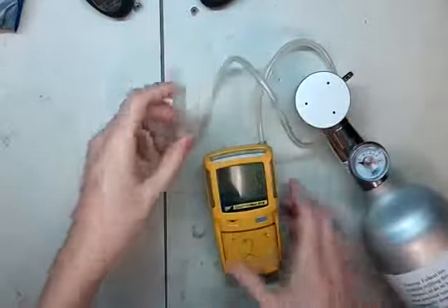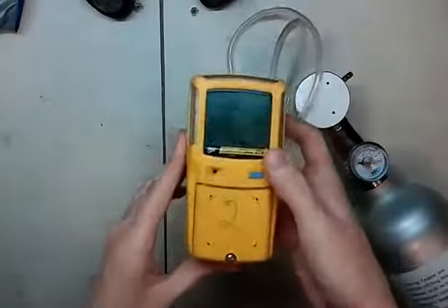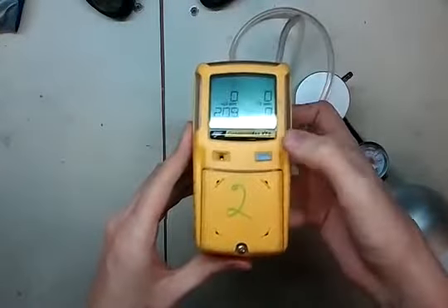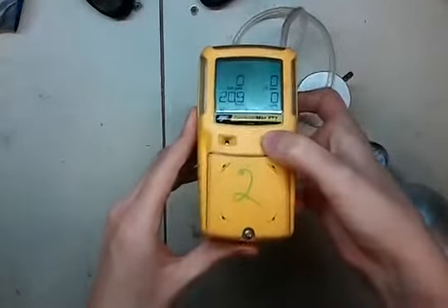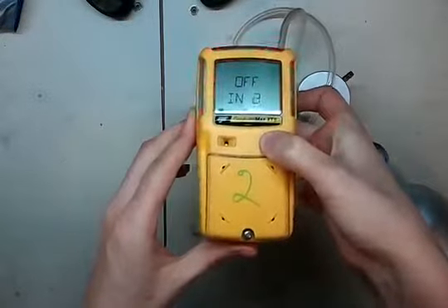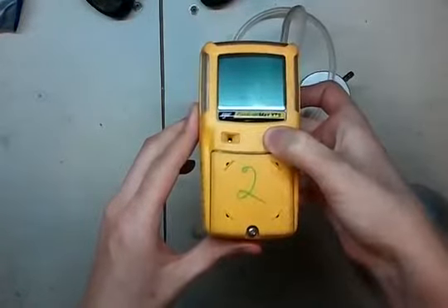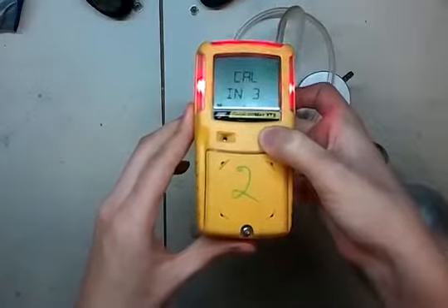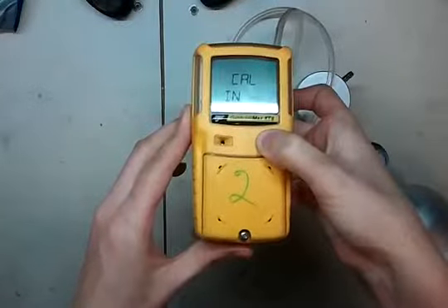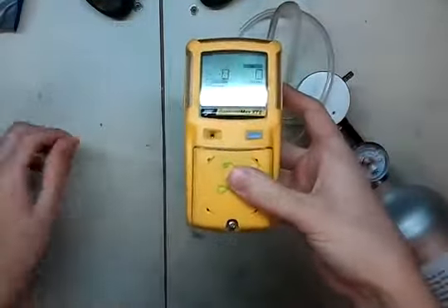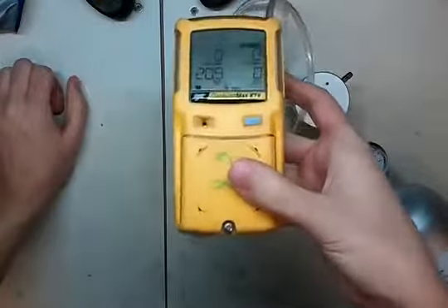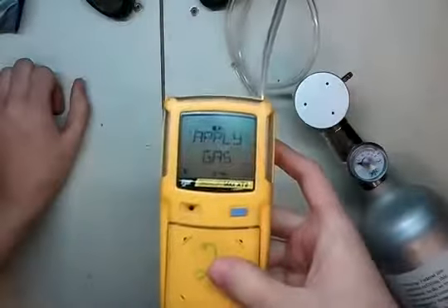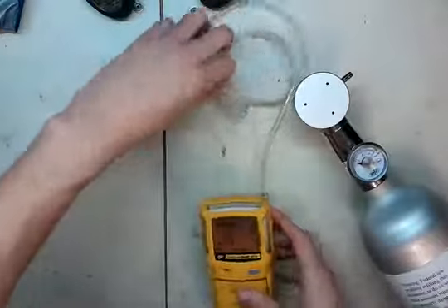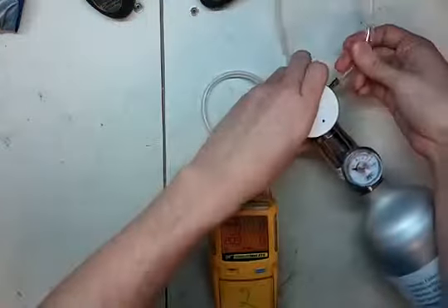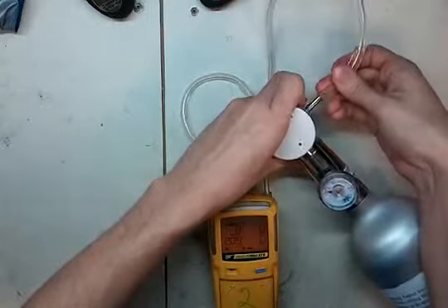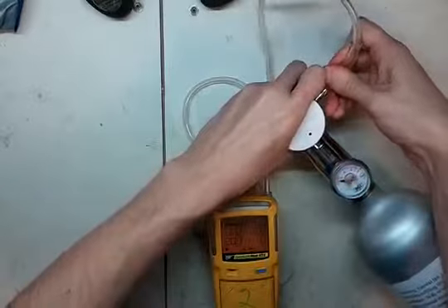What we're going to do is send the unit into calibration mode. To do that, we're going to hold it here, press and hold this button, and then keep holding it. It'll turn off. That's okay. Let it just keep going. Keep holding it. 2, 1. Okay. Now we're going to let it go through the zero process. That's what it's doing right now. Now it says apply gas. So, take the hose, put it right on your cylinder. There we go.